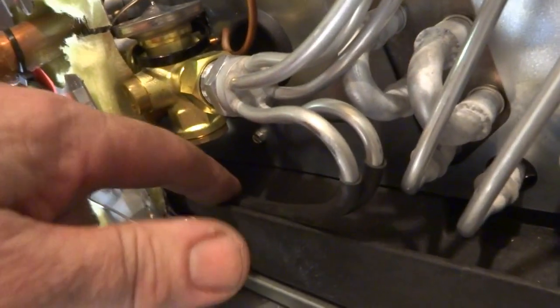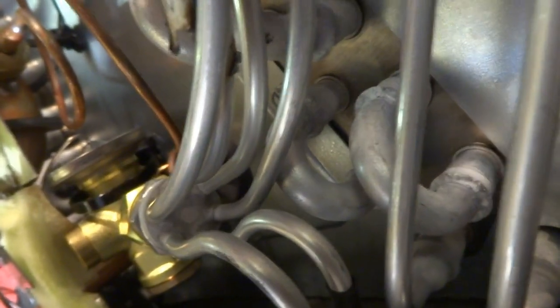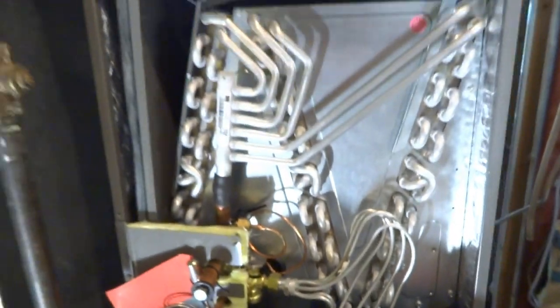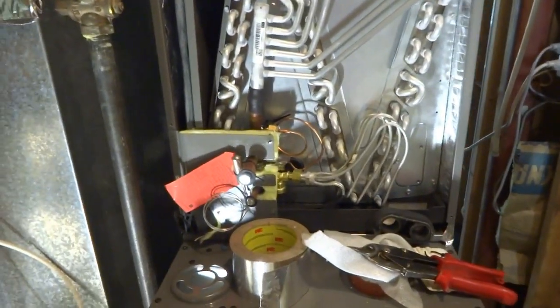These are coated. I'm not worried about those two. But these, you have to make sure none of them are rubbing, because they'll wear out. See, like that one there is rubbing on the unit. Gotta move it. Don't want it rubbing. Don't want anything rubbing. It'll last longer like that. If it's touching, it could vibrate and wear out.